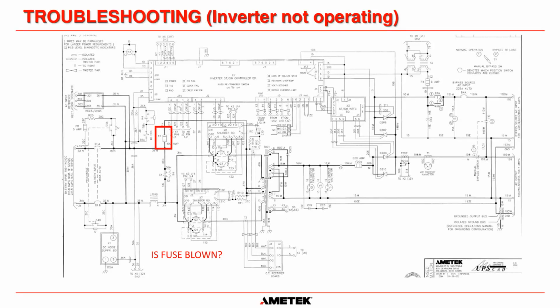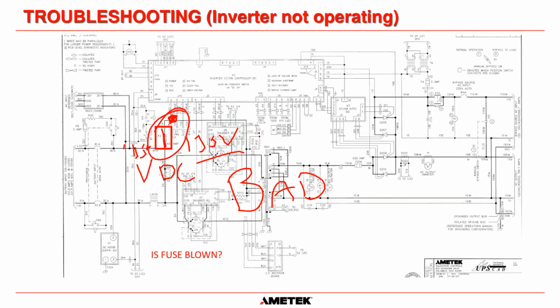Now, remember, we have DC going in. So the easiest way, if you still have the system energized, is with a Fluke on volts DC, to go on that side of the fuse with your red lead and go on that side of the fuse with your black lead. And if you have 135 volts measured across that fuse, then that fuse is, I hear you all shouting, bad. If this was a short circuit, if you have 135 on one side of the fuse, you have to have 135 volts on the other side of the fuse. So therefore, there should be no voltage potential across that fuse whatsoever.